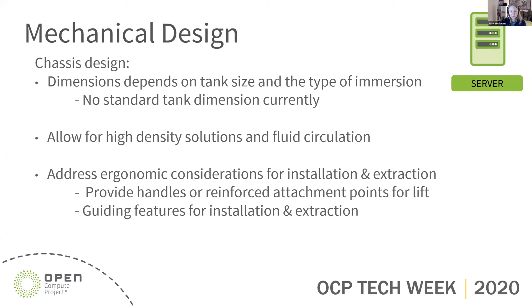For software, there are again differences here. We don't need any fans on the system in immersion. So removing those fans, and having the IT equipment or the system management detecting that the fans are no longer there, but it still can operate because cooling is still being provided. That's something that needs to be addressed for immersion systems.